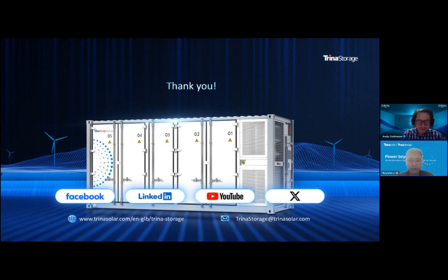Yeah, sure. As for the 12K cycle life, the testing conditions are that the cell is tested at 100% DoD, while considering a 0.5C charge and discharge rate. As of now, we have completed around multiple thousand, around 1,000 cycles for our 314 ampere-hour battery cells and 306 ampere-hour cells, and hopefully we will see more productive data from the battery cell as we test moving forward.